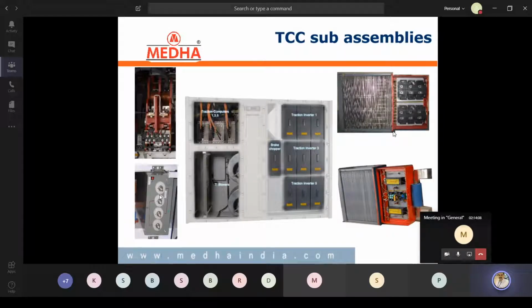So in general, whenever IGBTs are operating, the heat will be collected by the heat sink, and internally these pipes pass through the heat sinks. So the special coolant which is available inside the copper pipes collects that heat, and the hot coolant will come to the top, because this will be downside and it will be up. So the hot coolant will come to this side, and here the blowers take the outside air from the suction filters and blow it onto this phase module, so that these fins hold the air for some time, so that the cool air collects the heat from the pipe and the hot air will be exhausted from the exhaust filters. This is called heat pipe technology with forced air cooling mechanism.